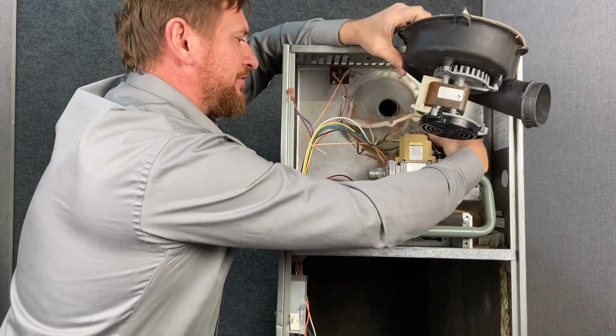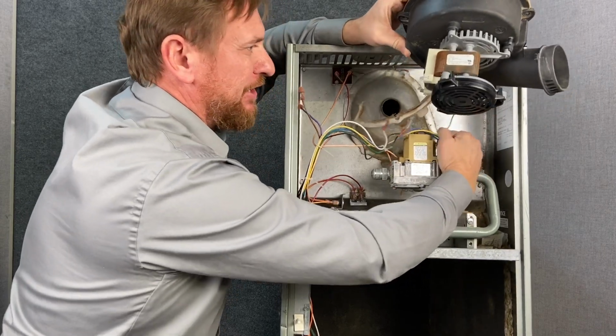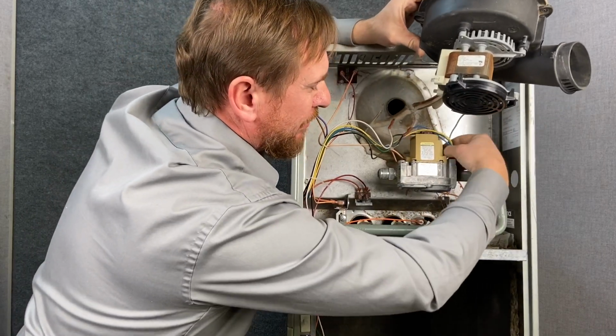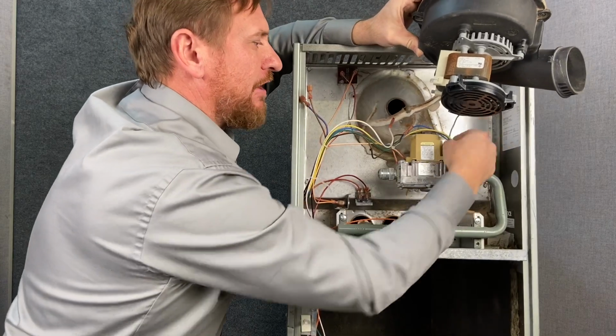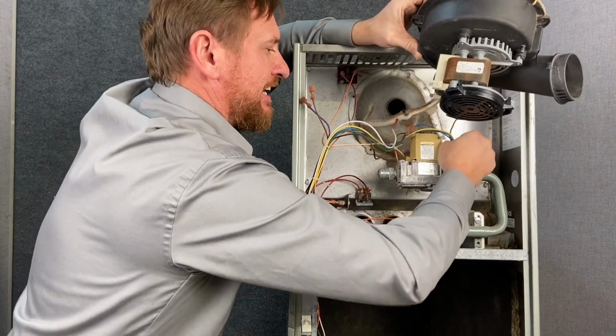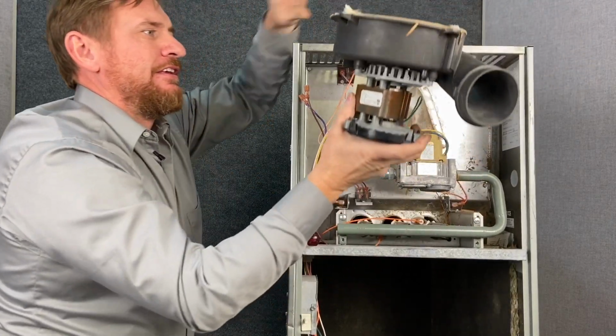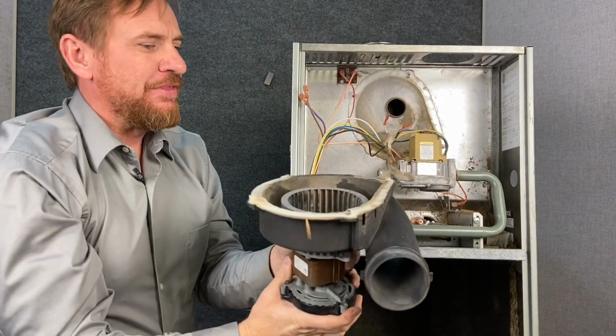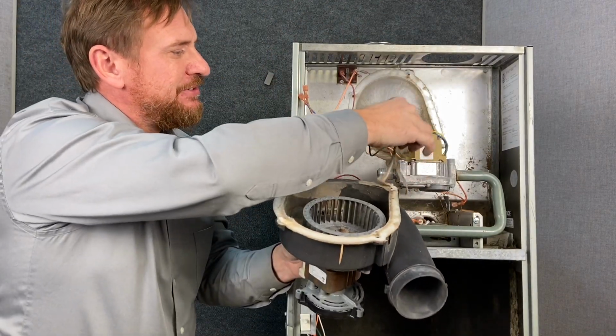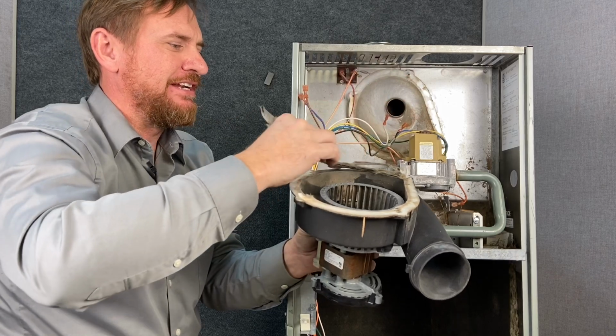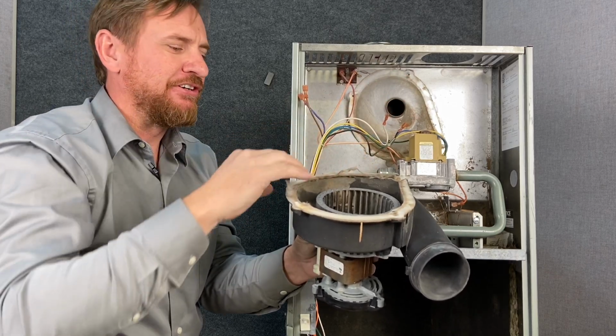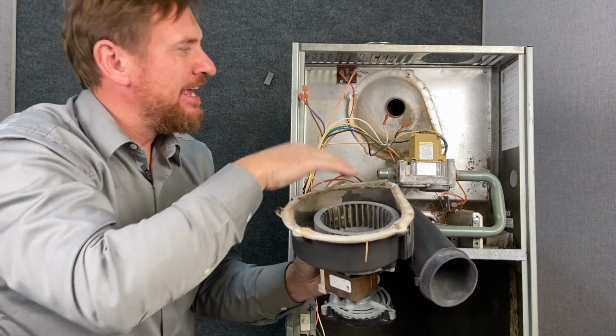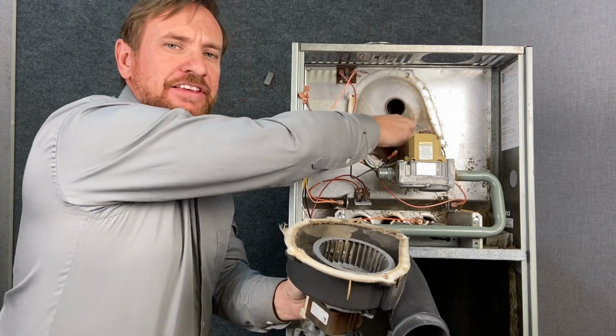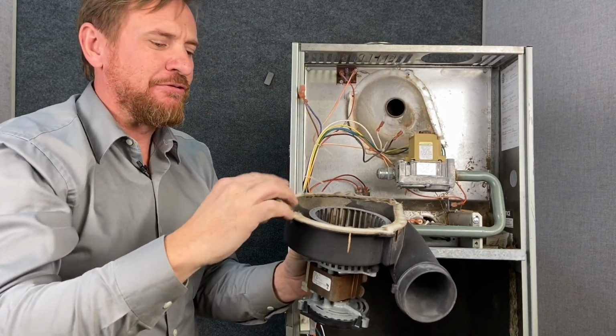And I did forget this one last little wire. There's a ground wire right here. So we can either take the ground wire off where it connects here or off of the motor. So I'm just going to pull it off of where it connects right here. So as I pull this off, one thing I really want to point out is notice this type of insulation right here. This is really a gasket material. It's a high temperature fiberglass. And because I pulled this off, this is now damaged. So I'd have to replace it.